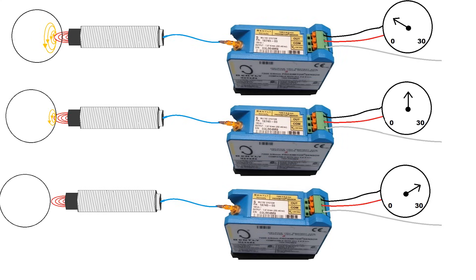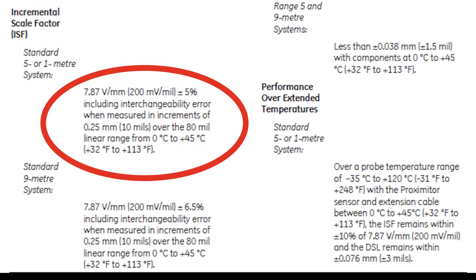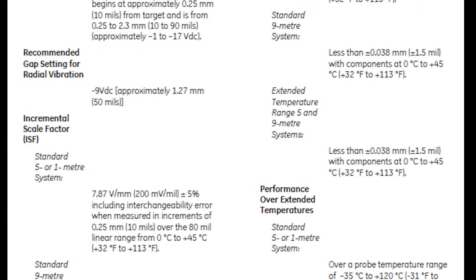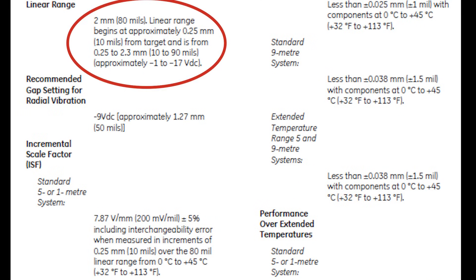This relationship between voltage and distance is defined as the incremental scale factor of the instrument. The most common ISF is 0.2 volts or 200 millivolts for every 1 mil of travel. This ratio only applies to a specified range of detection.